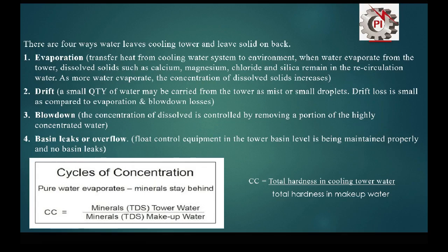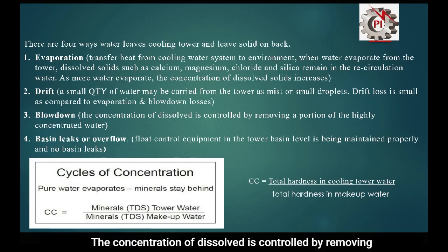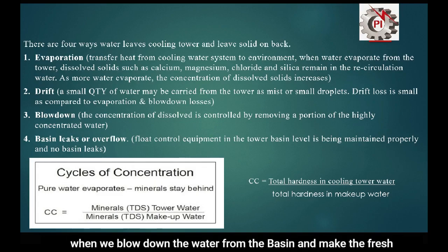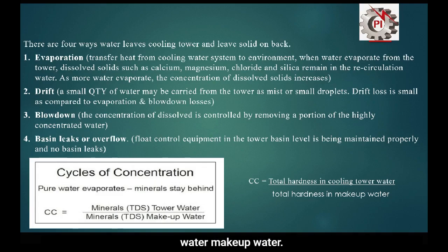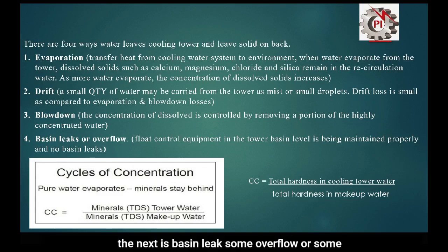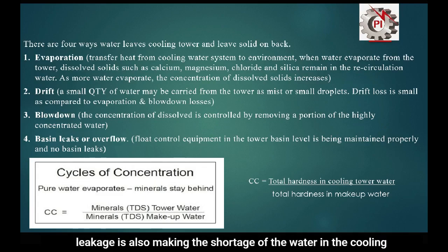Blow down. The concentration of dissolved solids is controlled by removing a portion of the highly concentrated water. Blow down means when the concentration of the solid particles increases, we blow down the water from the basin and add fresh water, makeup water, so that the solid particle concentration will be decreased in the basin. The next is basin leak or some overflow or some valve leakage, which also makes a shortage of water in the cooling tower.